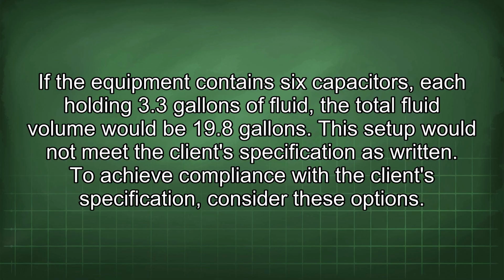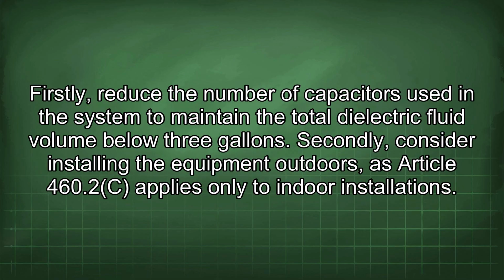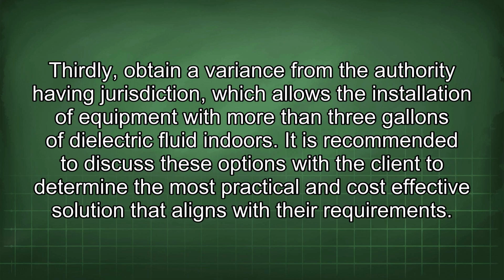To achieve compliance with the client specification, consider these options. Firstly, reduce the number of capacitors used in the system to maintain the total dielectric fluid volume below 3 gallons. Secondly, consider installing the equipment outdoors, as Article 460.2c applies only to indoor installations. Thirdly, obtain a variance from the authority having jurisdiction, which allows the installation of equipment with more than 3 gallons of dielectric fluid indoors. It is recommended to discuss these options with the client to determine the most practical and cost-effective solution that aligns with their requirements.